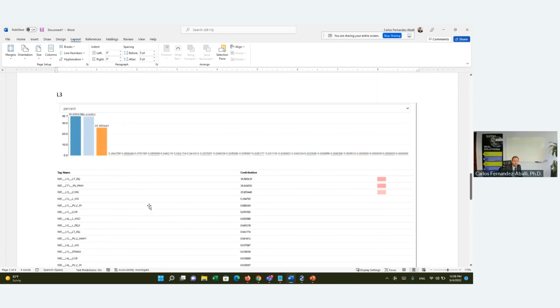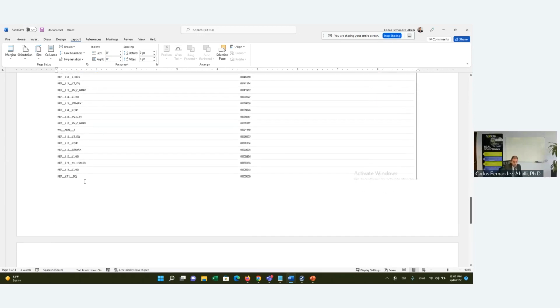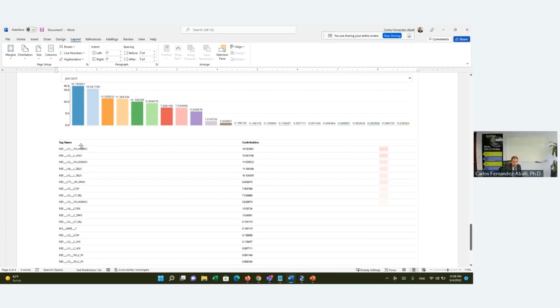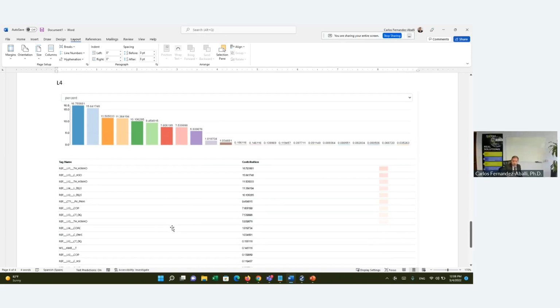Well, it's true of line 2, but it's no longer true of line 3. The heat transfer is more important in line 3 than the inlet pressure of the cooling tower. And in line 4 it's actually the enthalpy inlet into the throttle. And that's because line 4 is the cascade line. The system is in cascade, meaning it is line 4 that feeds the refrigerant into lines 2 and 3. So basically what this is saying is that the condensation temperature, or the condensation energy, is one of the key optimization variables, okay, which is also coherent with the enthalpy out of the compressor, okay?